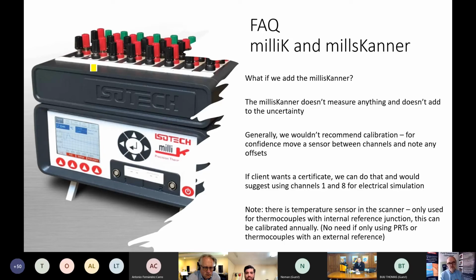So there's some evidence and some confidence. But if you want the assurance of calibration, we can do that. Of course, each channel you calibrate adds to the cost. So we would generally recommend calibrating the first and the last channel.